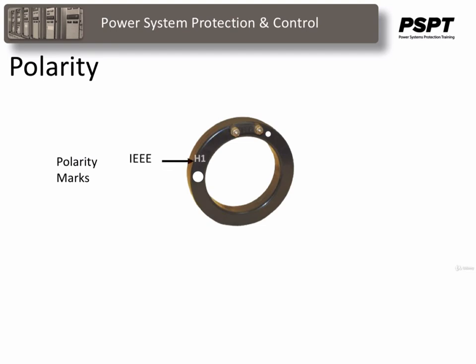The IEEE use a different standard, but it means the same thing. The spot side of the primary is H1 and the spot side of the secondary is X1. And in terms of the IEC, or International Electrotechnical Commission, they use P1 and S1 to designate the same thing as H1 and X1 that the IEEE do. Suffice it to say, we now have a terminal marked on the secondary, and we have a side of the CT marked with a spot of this particular donut CT.